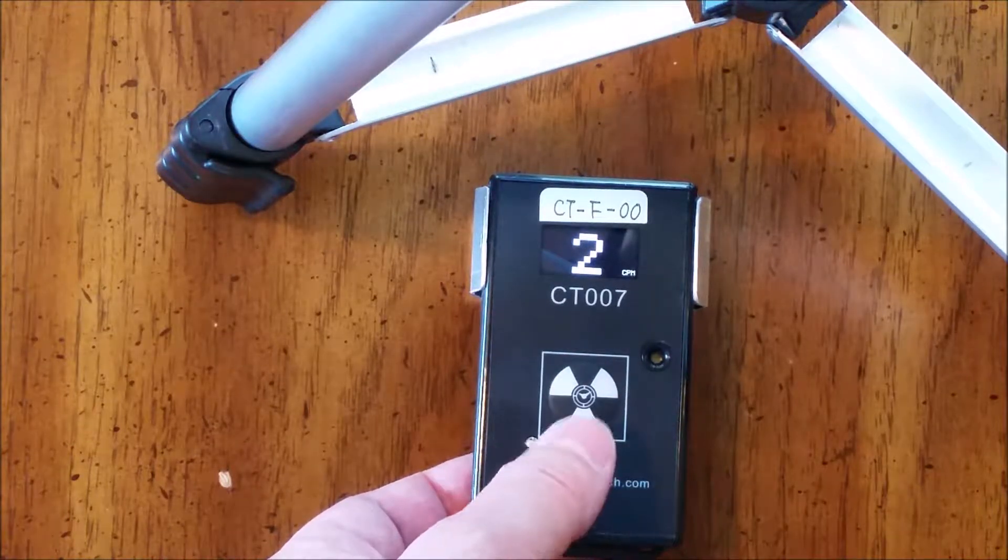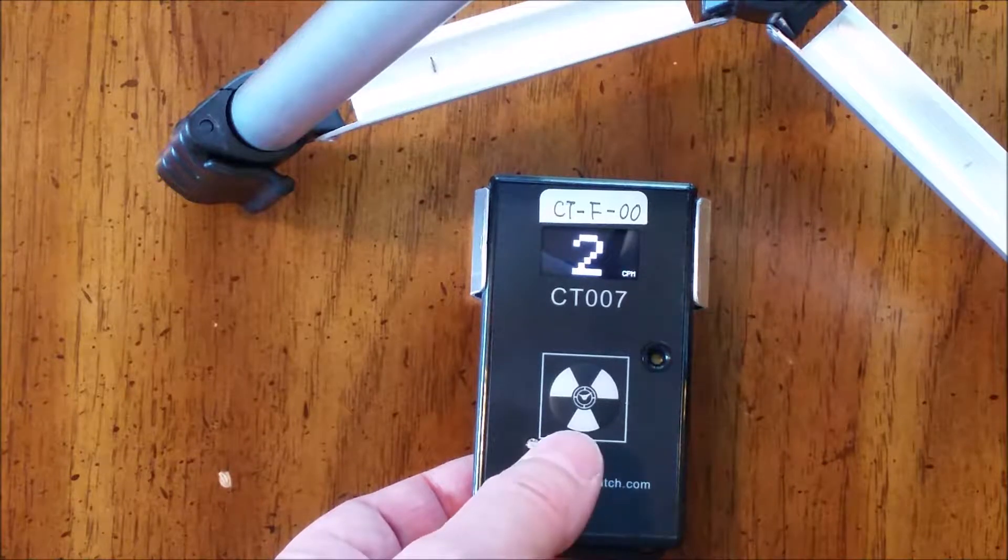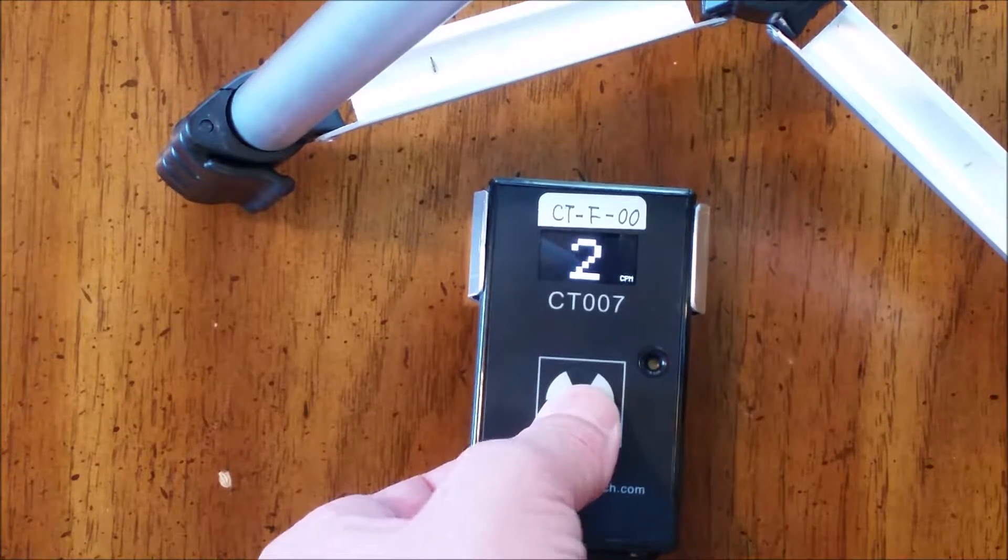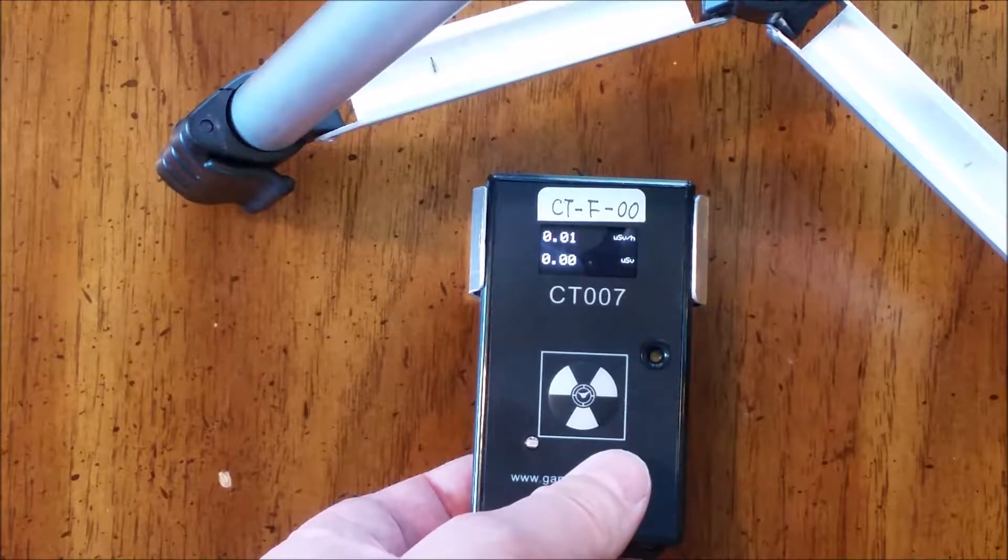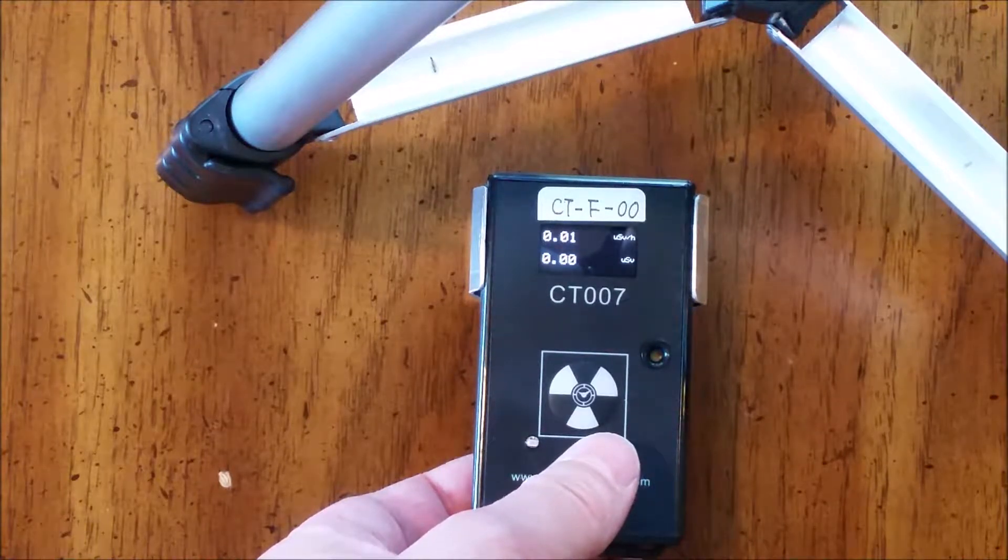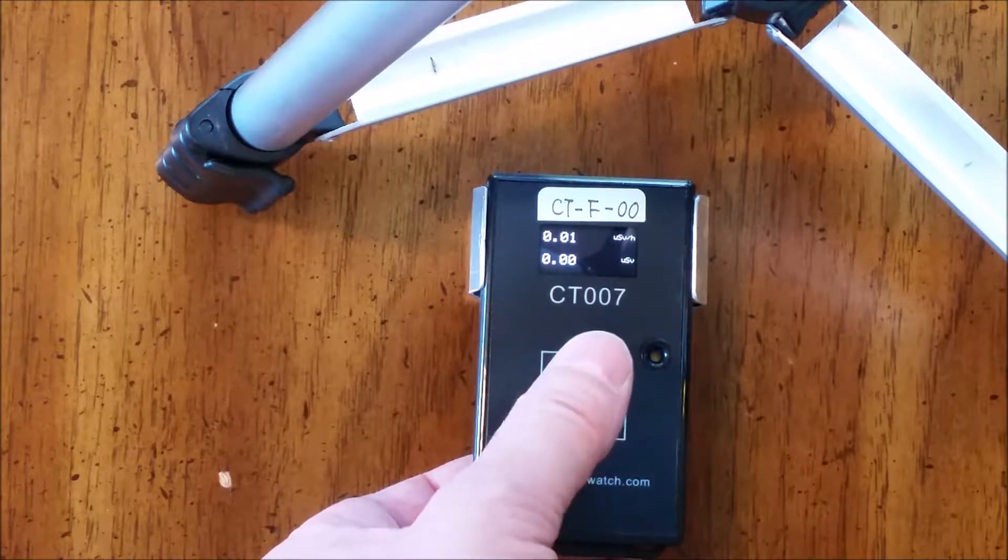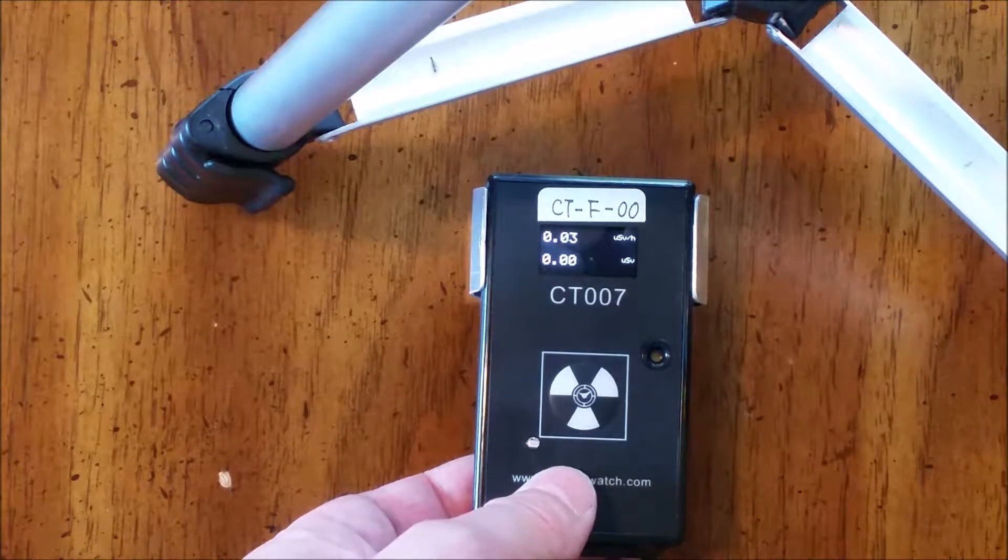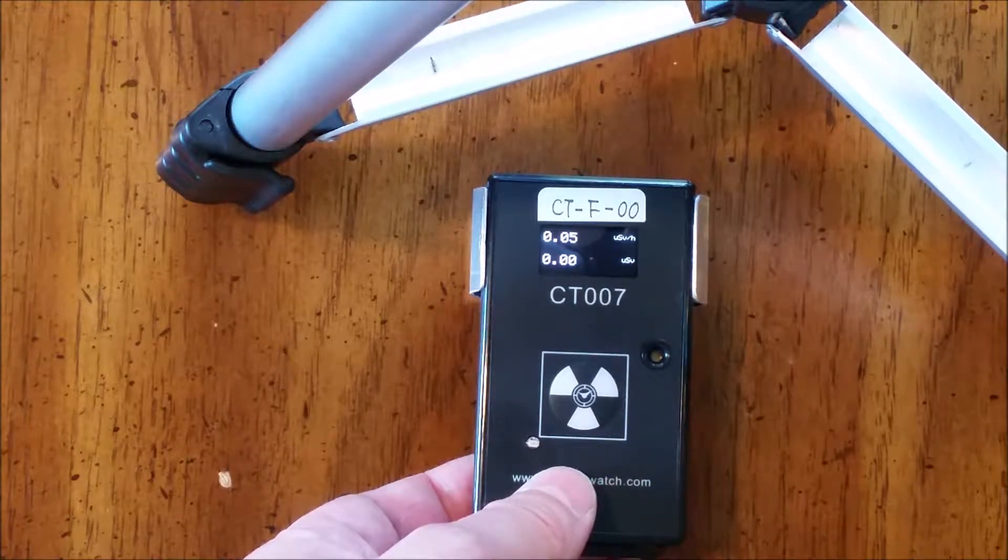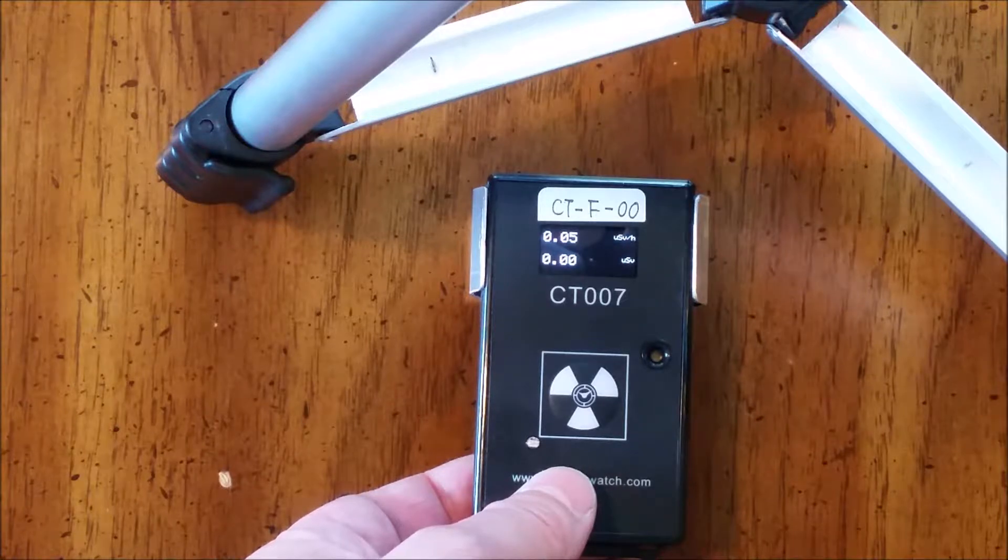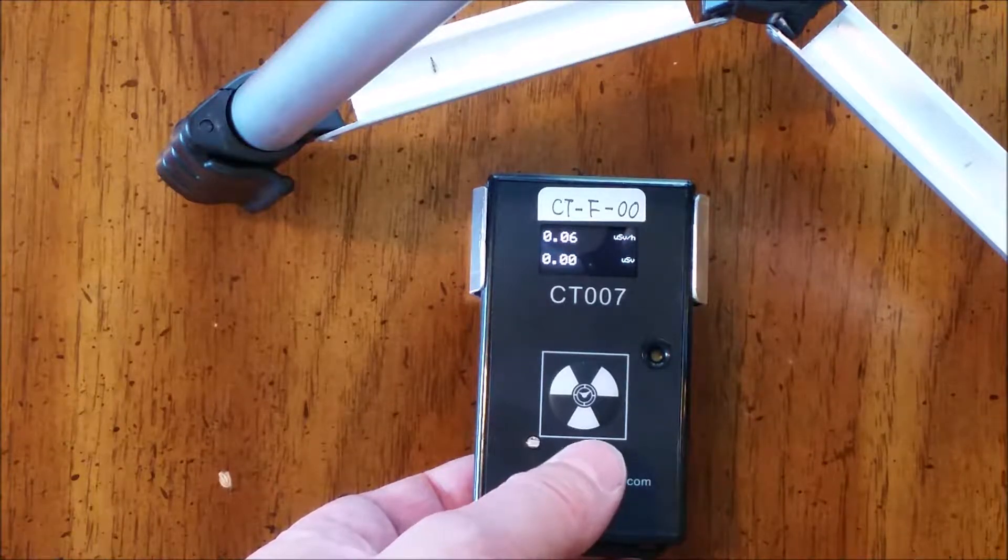A long press turns the unit on and it goes to the CPM display. Short pressing will toggle the display. So here we show the dose rate in microsieverts an hour. We can switch the display to millirem through our Android companion app.